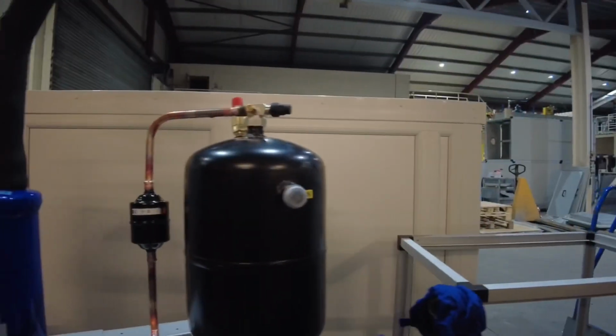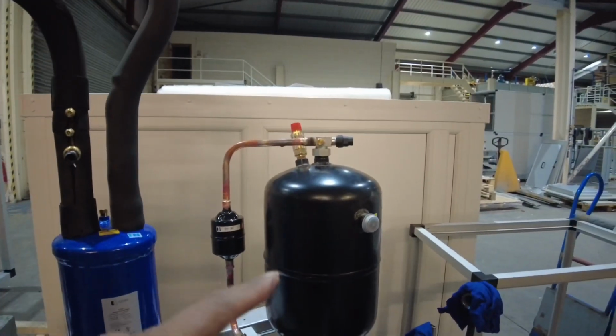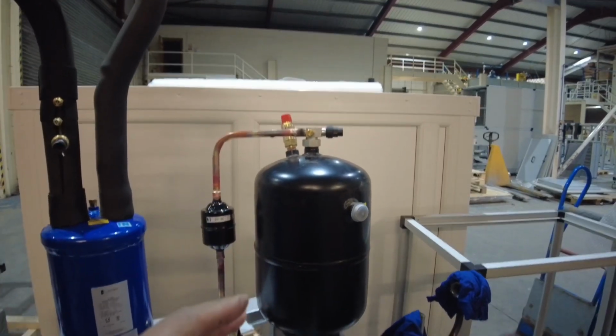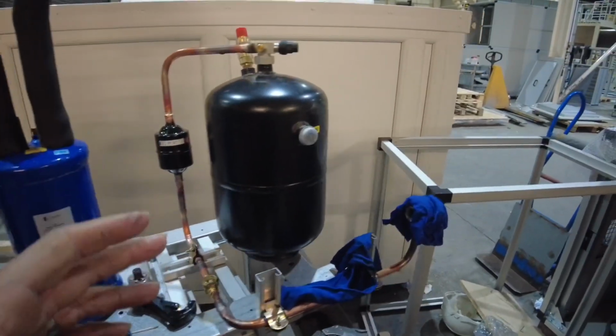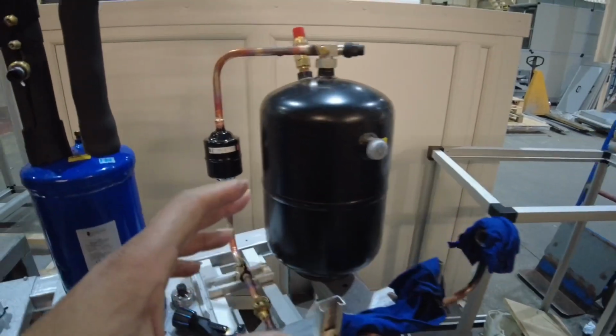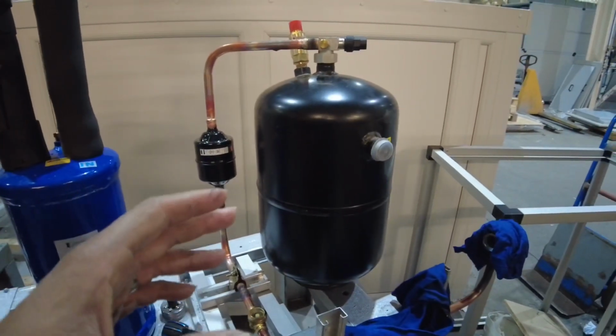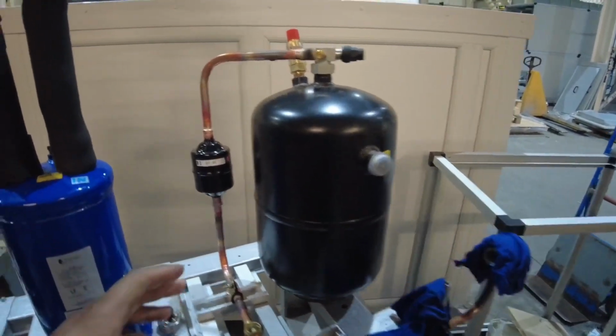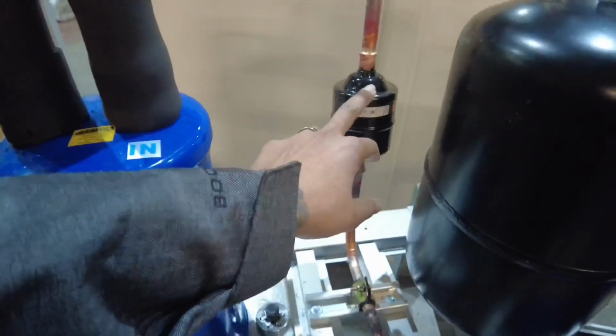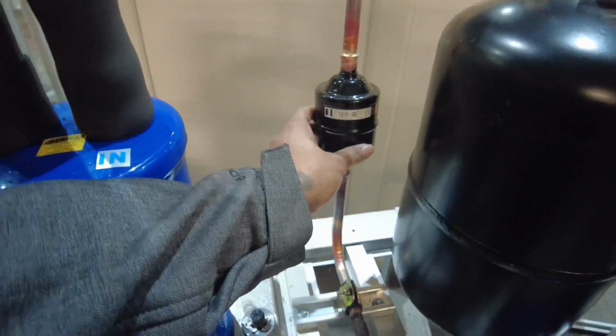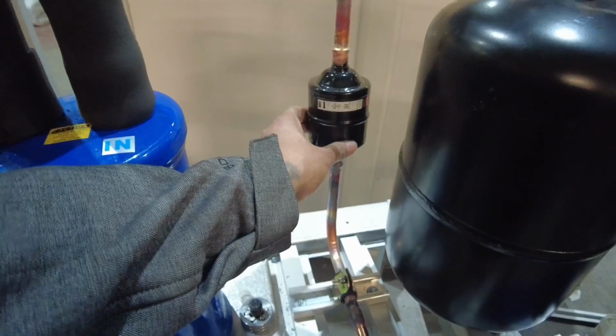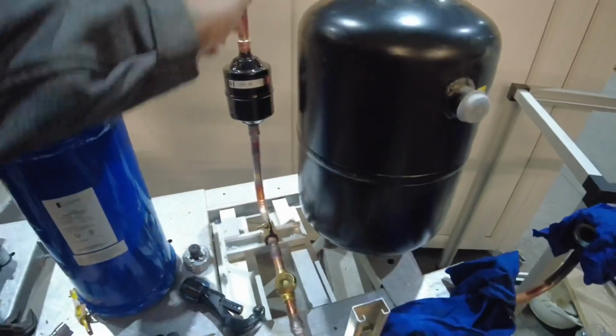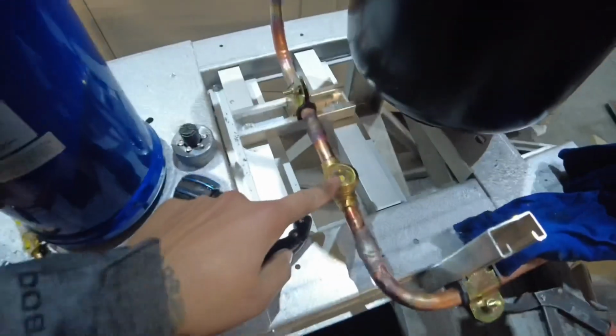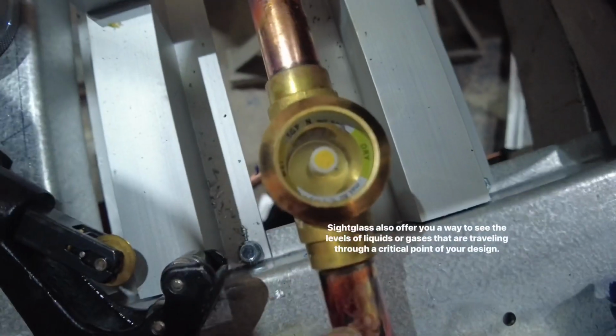There we go. So obviously talk to you about the liquid receiver. This holds a refrigerant charge in there. So yeah, that's where the refrigerant is charged. Extra anyway. Obviously you've got your dryer. Purpose of this is captures any moisture in the system as the refrigerant goes out there. This is your sight glass. So the thing that I'm pointing to there is a sight glass.